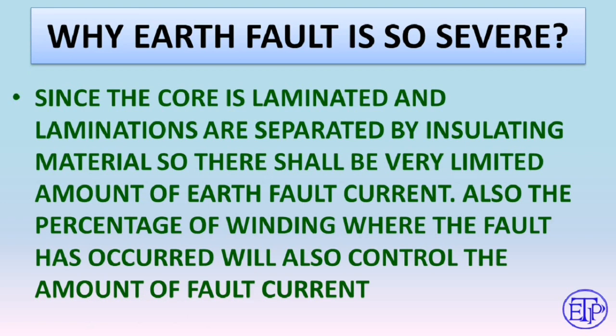Due to the high resistance, the earth fault current will be very low. However, the percentage of winding where the fault has occurred plays an important role. If the fault occurs at 100% of the winding, 100% voltage delivers the fault current. But if it occurs at 10% of the winding, only 10% voltage drives the fault current, making the earth fault current very low.